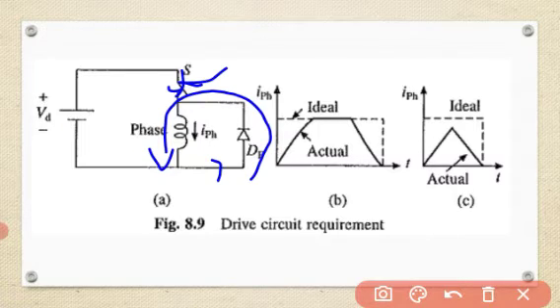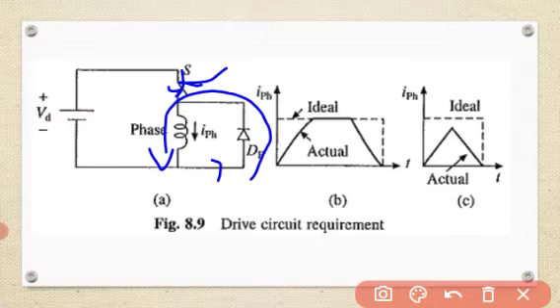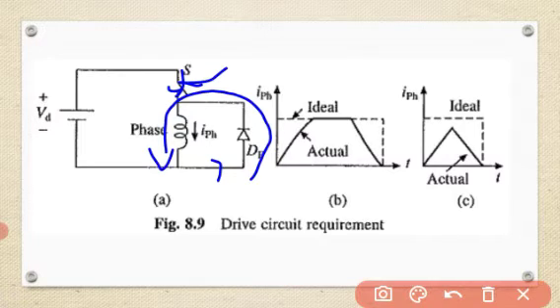Motor torque, which is a function of IPH (phase current), builds up and decays in the same manner. Now, in order to maximize the torque capability of a stepper motor, the drive circuit should be such that the current builds up and decays as fast as possible.